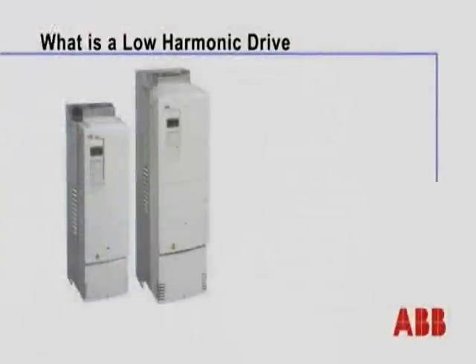Today what I'd like to do is take an opportunity to discuss with you a little bit about our ACS800 Ultra-Low Harmonic Drive. First of all, what is an ultra-low harmonic drive? A low harmonic drive is basically a standard AC drive with a unique front end that allows us to reduce the harmonics imposed on the AC line.